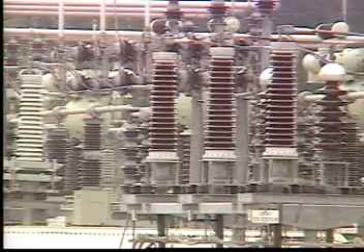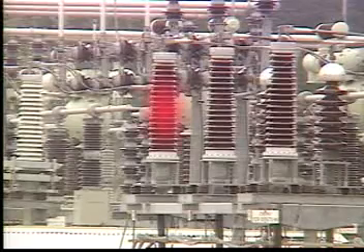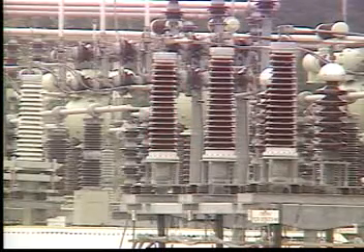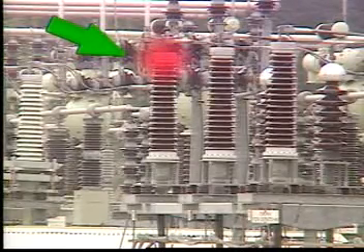Not all electrical discharge is destructive. Non-destructive or nuisance corona may result if there are sharp points or edges on the conductors of high-voltage lines. Electrons may jump off these points, especially in humid weather. Similarly, insulators that have cracked or broken bells may have surface tracking over the broken areas and corona from the sharp edges. This may not be a serious problem — it may be explained by sharp edges, burrs, or points at the ends of the insulators, which can give off a nuisance electron spray.